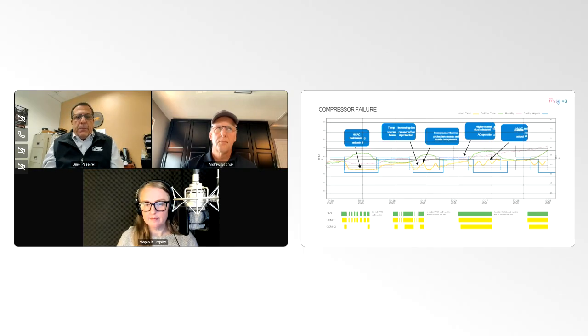Using a product like MISA makes that process much easier, because you're able to see multiple units, multiple equipment, multiple set points, and temperatures from one spot instead of walking a giant facility or space. And then it's obviously the cleanliness of the units. It's the coils, the filters. A lot of rooftops for retail space bring in outdoor air, which means that there's an economizer component where you could utilize the cool or cold outdoor air to help cool the facility, making sure that is operating correctly. Things of that nature, I think, are the best way to go about it.